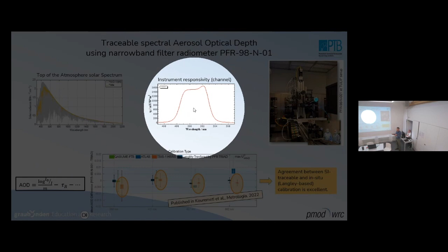It's in a huge clean room. It's based on tunable laser sources where you can actually measure the instrument responsivity versus wavelength. So you get the transmission of the instrument for all the channels at which it's measuring. And then using that information, your ground-based measurements become traceable to SI.